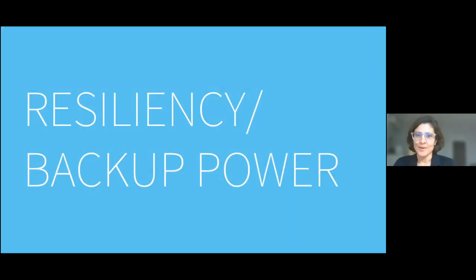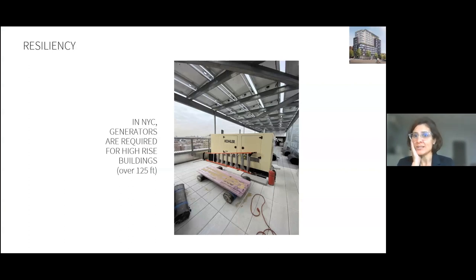Okay, resiliency and backup power. Now we will discuss another challenge that we are encountering with the electrification of our residential buildings, which is the requirement for backup power for such buildings that are over 125 feet in height, which is code required. The backup power is required for life safety elements in those buildings, such as elevator, fire pump, and emergency lighting. Unfortunately, right now, the easiest and most economical solution to meet this requirement is the provision of a generator, which is reliant on fossil fuels.